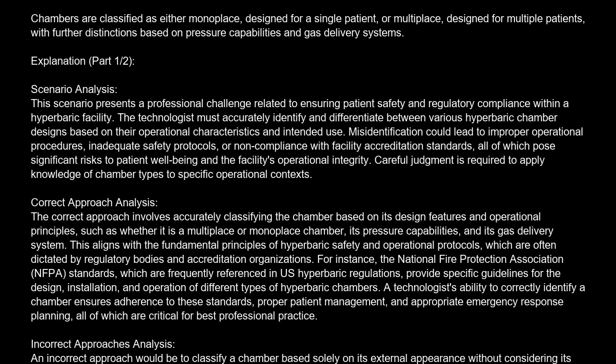This aligns with the fundamental principles of hyperbaric safety and operational protocols, which are often dictated by regulatory bodies and accreditation organizations. For instance, the National Fire Protection Association (NFPA) standards, which are frequently referenced in U.S. hyperbaric regulations, provide specific guidelines for the design, installation, and operation of different types of hyperbaric chambers. A technologist's ability to correctly identify a chamber ensures adherence to these standards, proper patient management, and appropriate emergency response planning, all of which are critical for best professional practice.